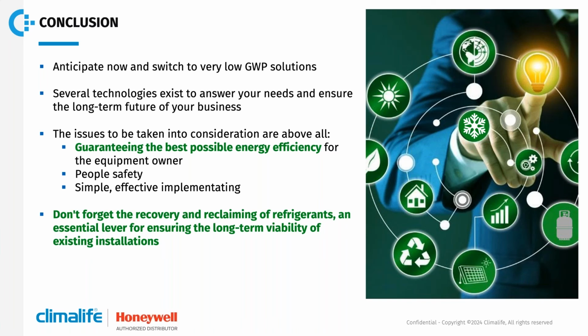Several technologies exist to meet your needs. HFO and HFO blends are authorized without limit until at least 2050, except for domestic refrigeration in 2026 and chillers less than 12 kilowatt in 2032. We will also have an exception for plug-in, monoblock, self-contained or split systems less than 12 kilowatt for air conditioning and heat pump applications.